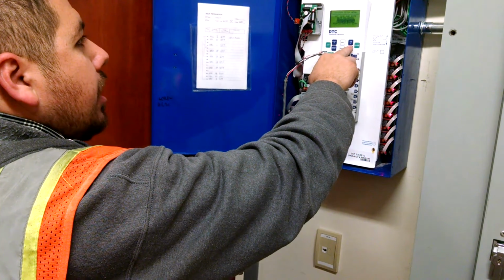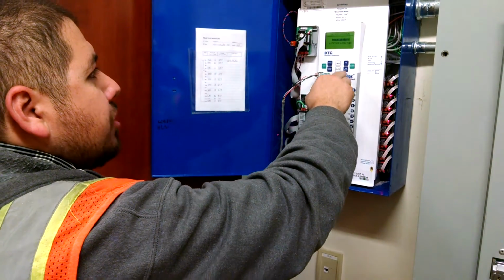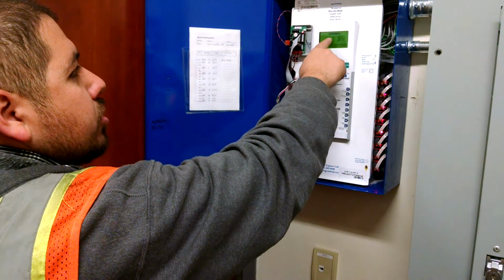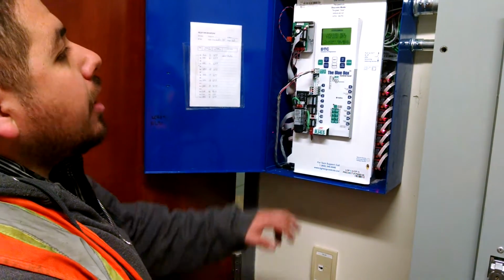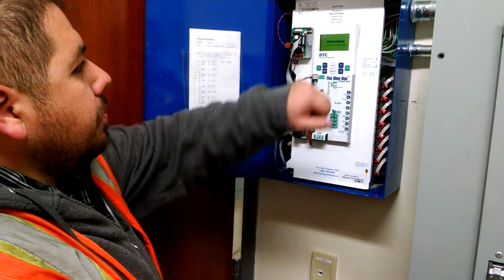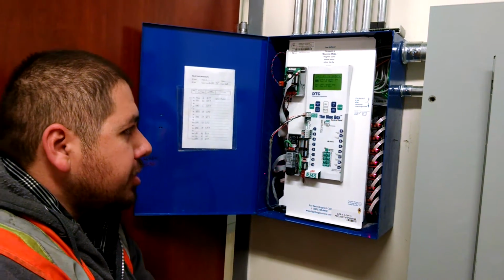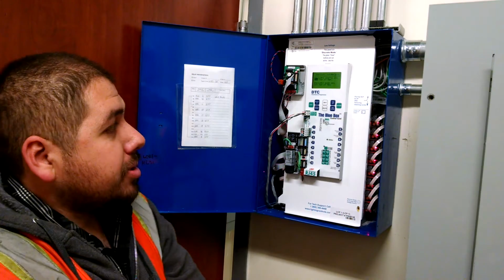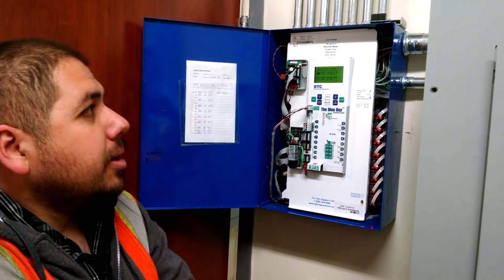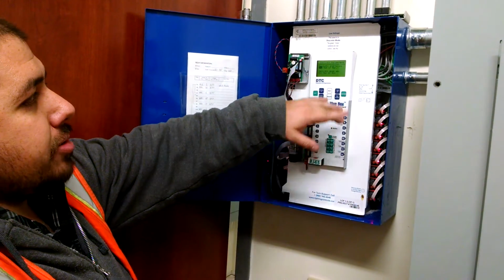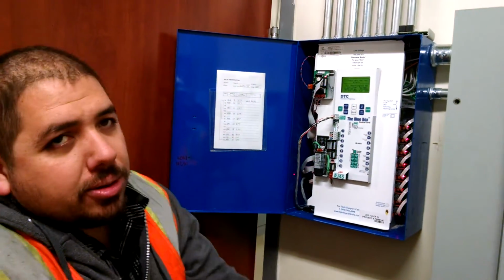Okay. If we want to go to system options now, select location for the Astro Clock, list of cities. It knows we're in Denver, Colorado, which is latitude of about 40. It's 39 point something. So that's going to be the Astro Clock information. And finally, daylight setup. Panel knows daylight savings time based on this information right here. So if the government ever decides they want to change daylight savings time again, you can always adjust when daylight savings starts and when it ends in that menu there. That's pretty much it for this panel and what we're doing on this site.